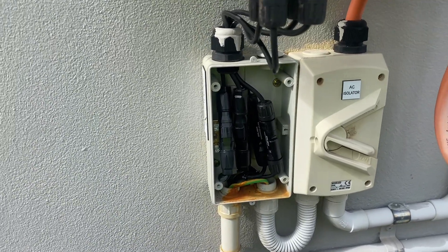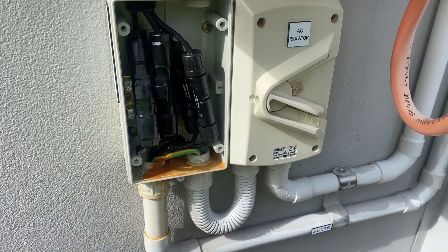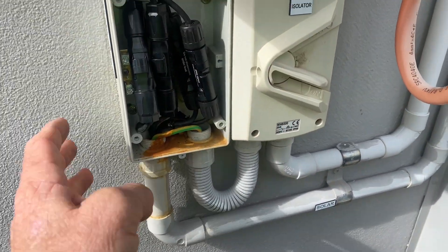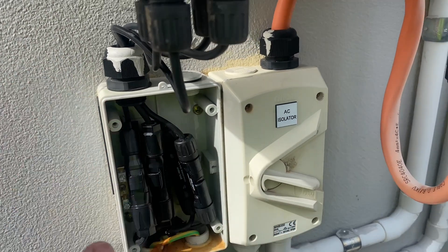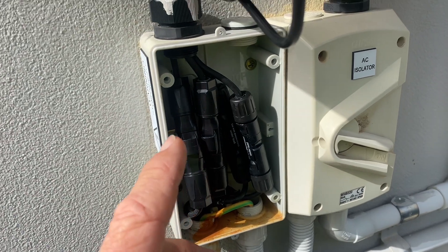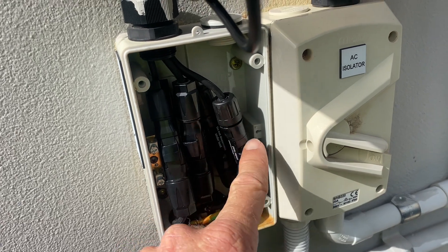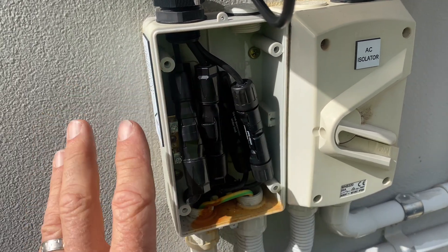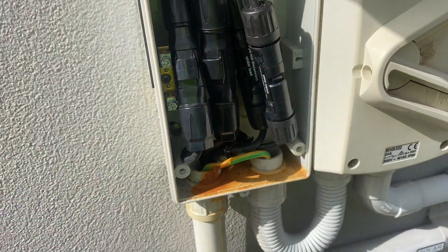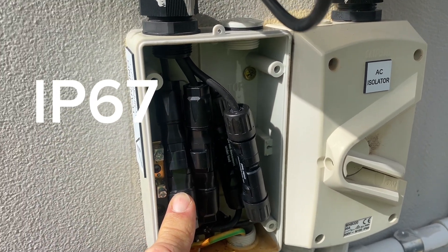What I've ended up doing here is, because we've got a water ingress issue, if I put another AC isolator in there it's just going to fail again. The way this has been installed, without a lot of stuffing around, I can't make that water resistant. So because there's still going to be water going in, I've used the proper MC4 connectors — which is what we use up on the roof — and they're completely water rated, so we won't have any further issues there.